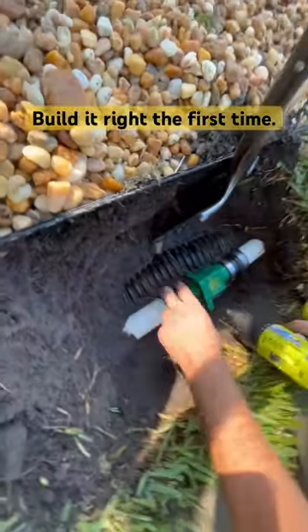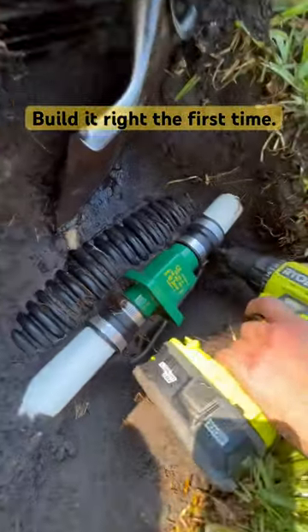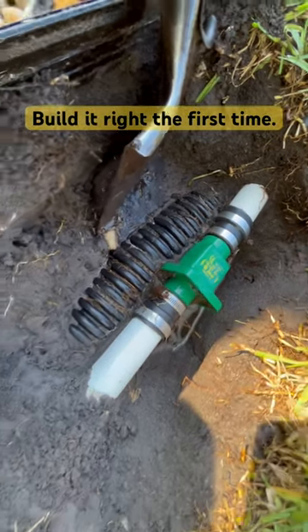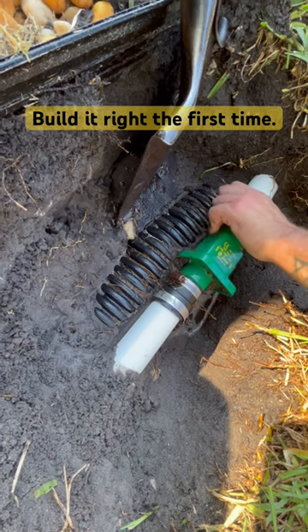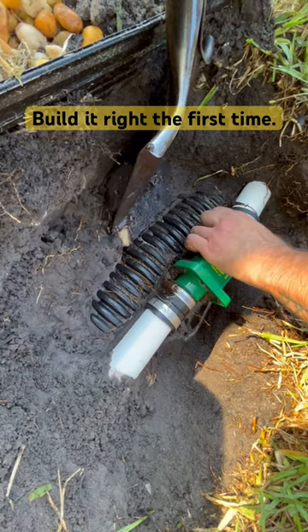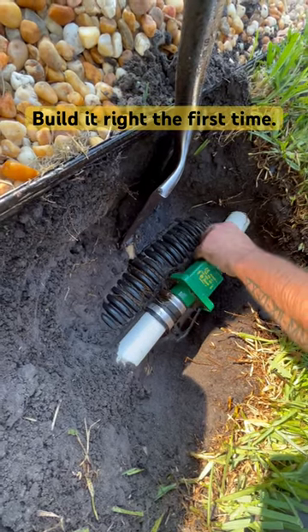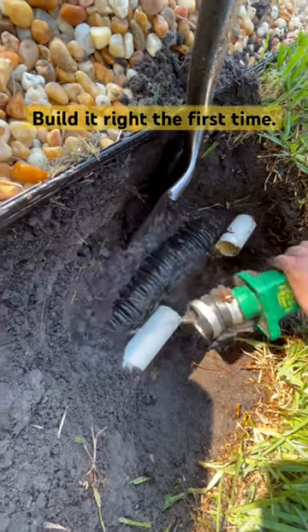This is a perfect example of how not to install a check valve. This one happens to be a flapper check valve, meaning it has a flap that opens up. And if you put these on their side, that flap basically is useless.